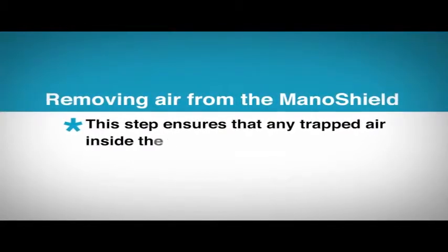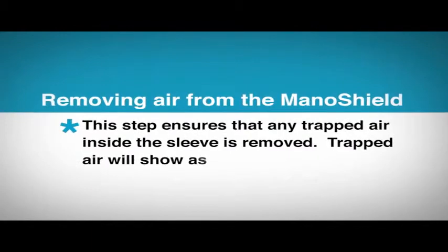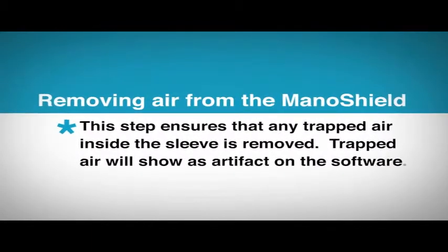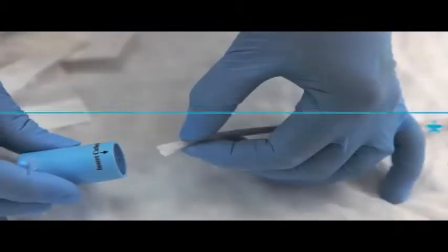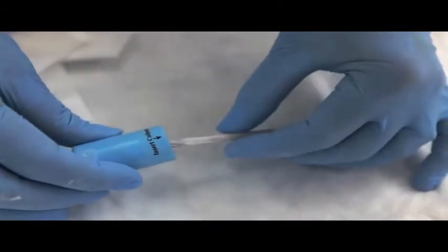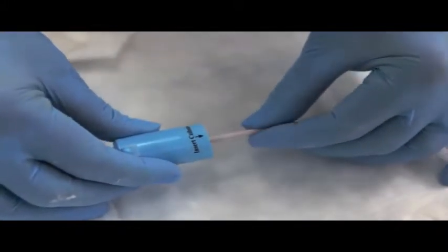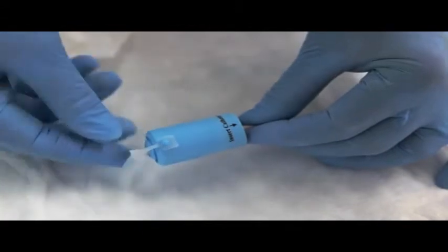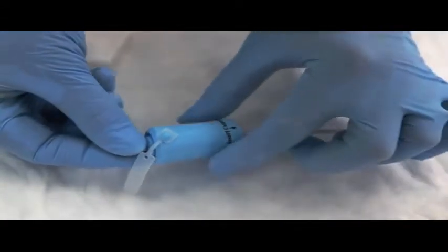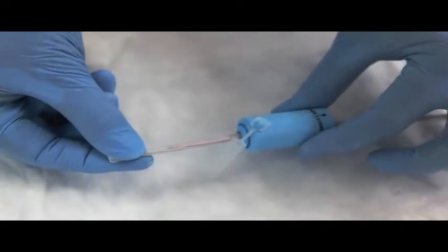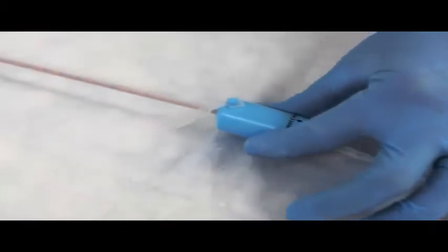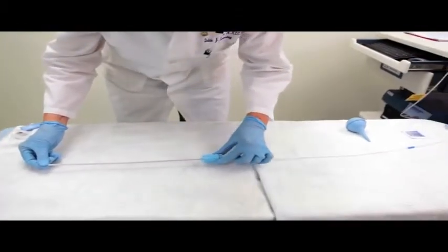Removing air from the Manoshield. This step ensures that any trapped air inside the sleeve is removed. Trapped air will show as artifact on the software. Holding the plastic blue slider with the silicone tab pointing away from the catheter, gently insert the distal tip of the catheter with folded back sheath tip into the slider. In a smooth motion, pull the slider up the entire length of the catheter until it reaches the blue cuff of the sheath. Do not pump the slider back and forth.